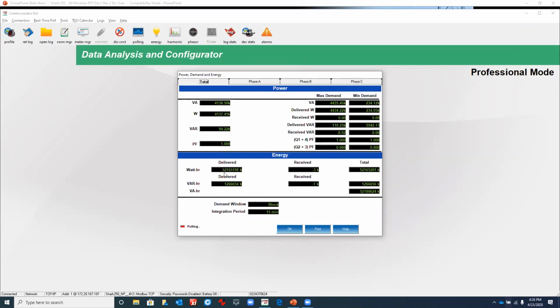Also on this screen, we actually see what's on the registers. If you want to take a screenshot of the energy readings or register readings on the display of the meter, you would go to this screen. This is one screen that you can look at to get that information. It also provides the demand window. This is set for block demand. That means energy stored in 15-minute blocks, as opposed to rolling demand. Those are the two formats for demand, rolling and block. Depending on your perspective or who you are, utilities like to use rolling demand as a selection, and some other customers might want to use block. So it varies on your choices, but this is the screen that you will get from the power, demand, and energy screen.